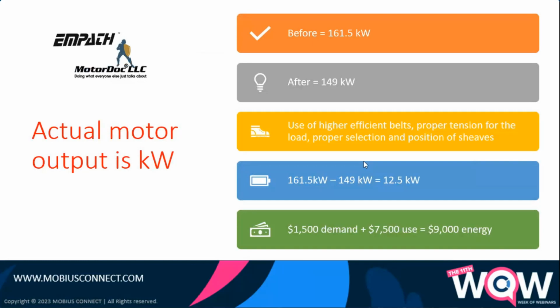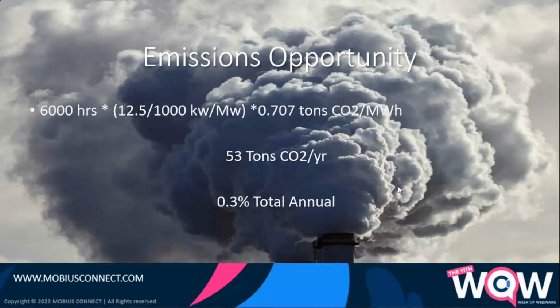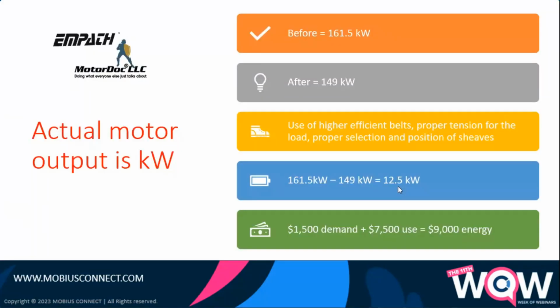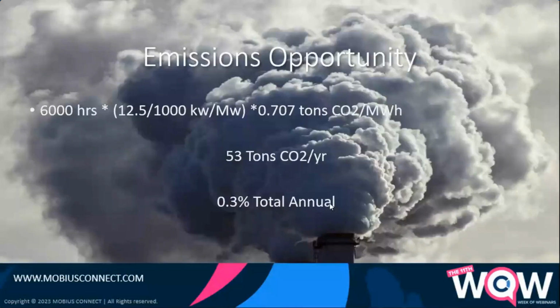So when we take a look at it, I'll go with the output because we had some bearing issues that weren't addressed. So before was 161.5, after was 149 kilowatts in the load. That is a significant drop. That's 12.5 kilowatts. So by doing that, we reduced the damage occurring to bearings. They were actually breaking shafts on this application because the pulley weighed more than the motor. Now going down to the smaller pulley, they got more life out of the machine. As a matter of fact, going from a failure every 6 months, that was 2 years ago, and they haven't failed since. It seems to be running like a champ, while also reducing energy costs by $9,000 for that application. And 53 tons of CO2 per year, which is 0.3% of the annual.